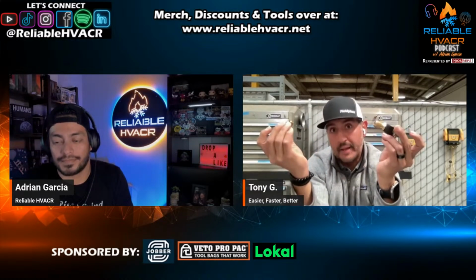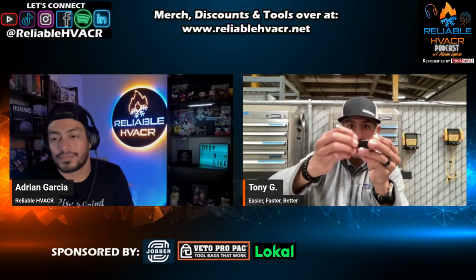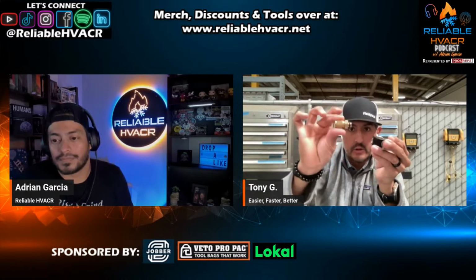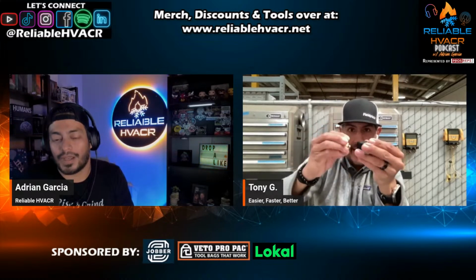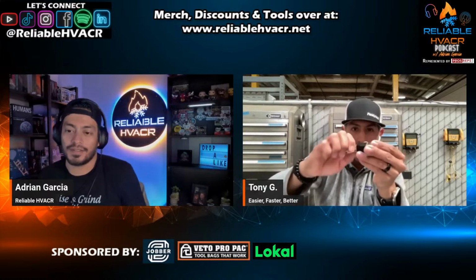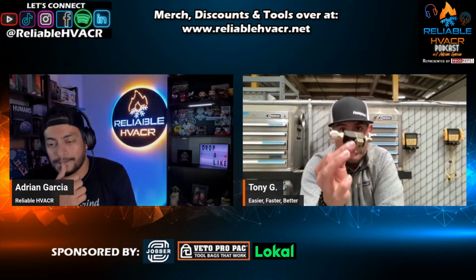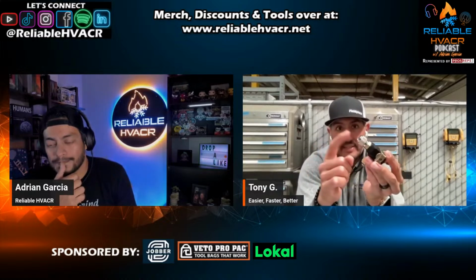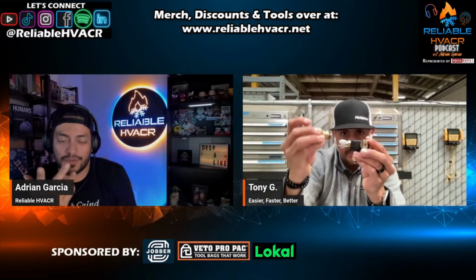And again, we're talking about space as a premium sometimes when we're working on these service ports. So the Fieldpiece VCRT has the ability to unscrew the 1/4 inch fitting and take your 5/16 inch fitting and use it for the same tool. So you don't need two tools for both those fitting types. You just need the VCRT and then the 5/16 inch fitting adapter to swap back and forth. You swap it out, exactly.